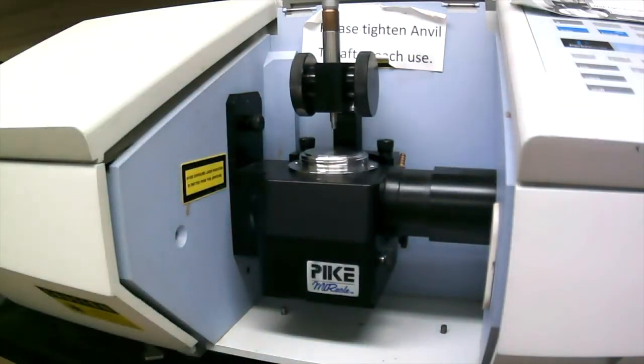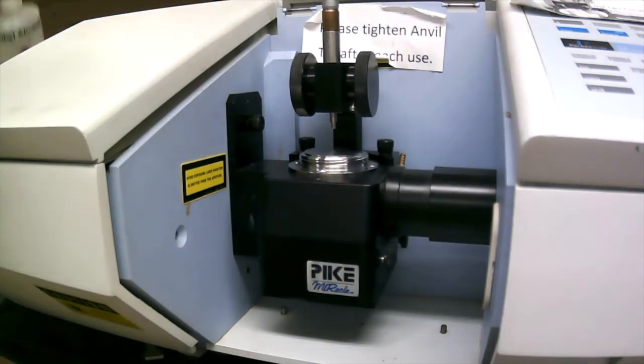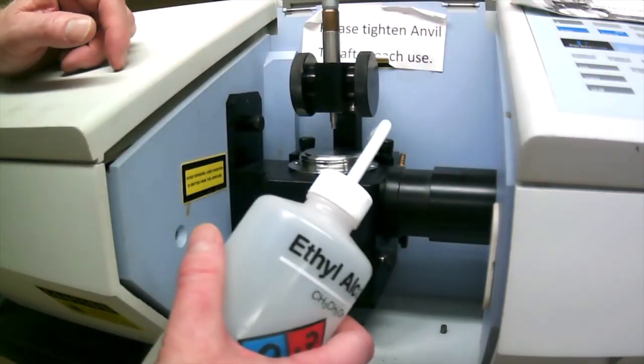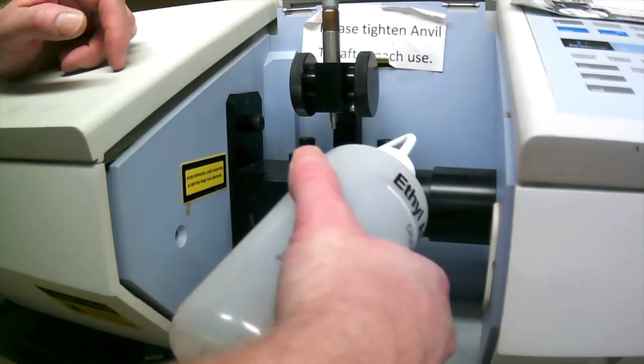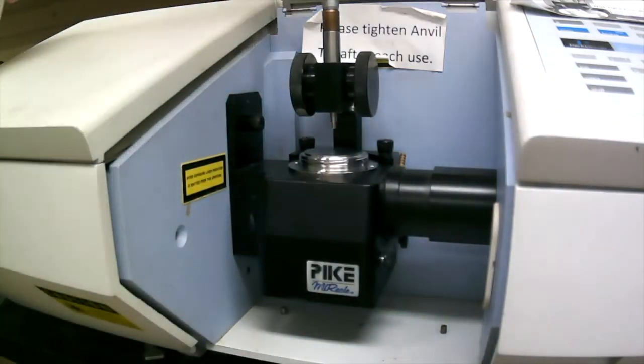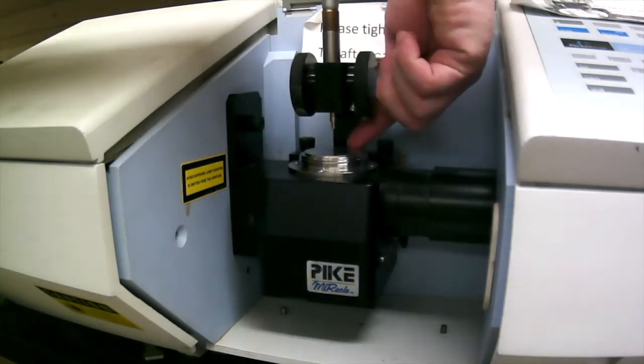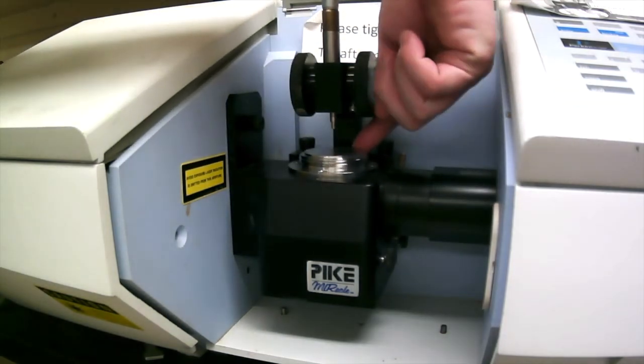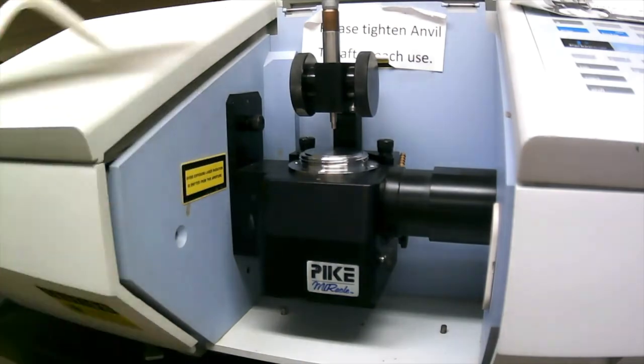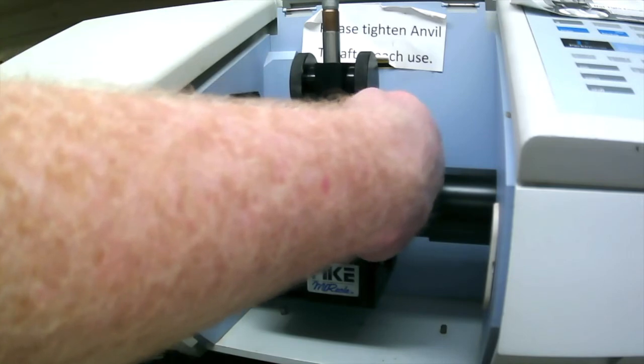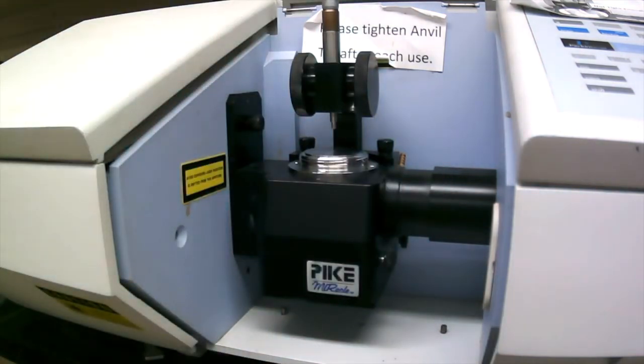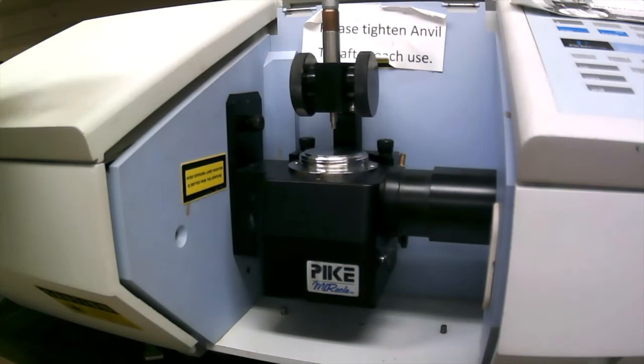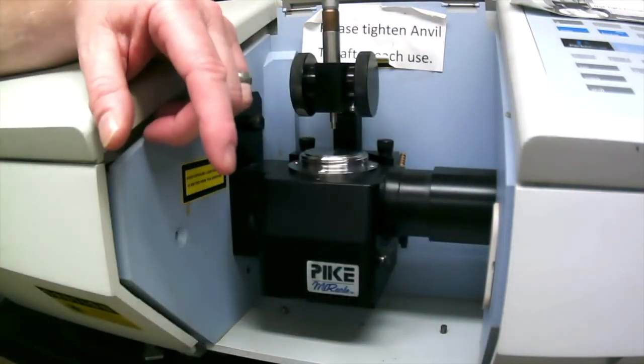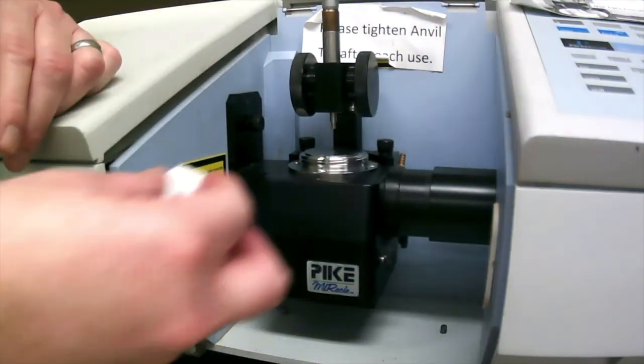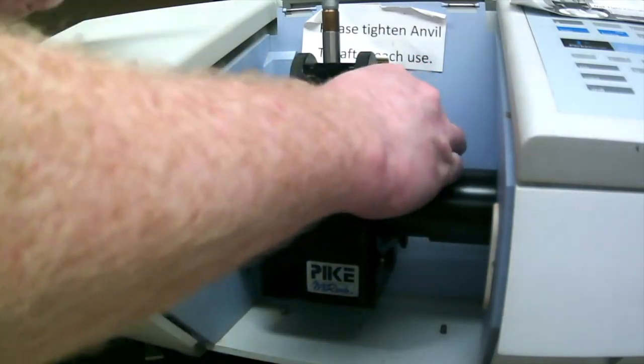Got it. And the reason why I don't want you to squirt the ethanol directly onto here is because you could squirt a lot and it can get back here. And if it gets back into this area right here, behind the disc, the puck, we call it, you can get a lot of ethanol back there, and it's not easy to chem wipe it out. What happens over time is it'll just slowly start evaporating, and the fumes will be in your spectrum, in your background, maybe. And so don't do that. So, and then you'll notice I just cleaned off the ethanol we ran. We won't normally run ethanol, but that's sort of our cleaning solvent.